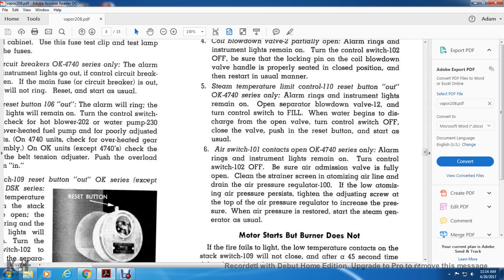Clean the strainer screen of the atomizing air and drain air pressure regulator 100. If the low atomizing air pressure persists, tighten the adjusting screw at the top of the air pressure regulator to increase the pressure. When the air pressure is restored, start the steam generator as usual.